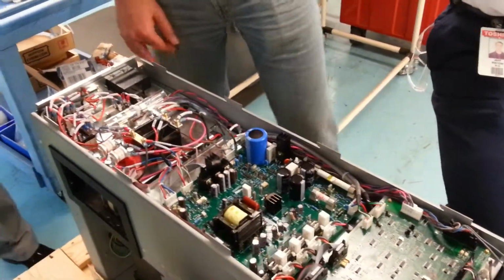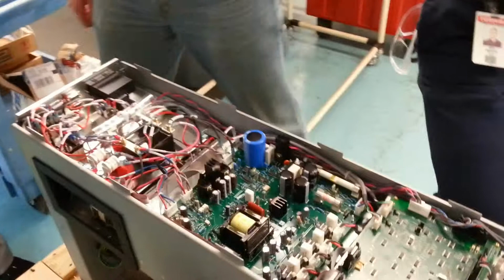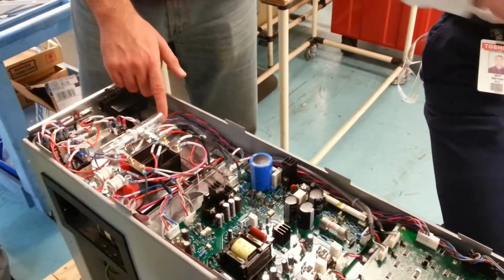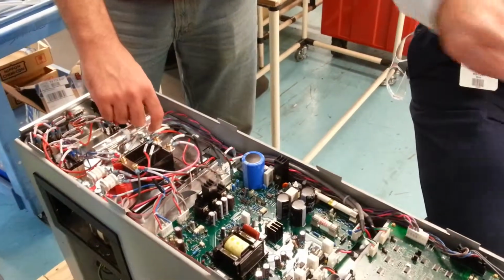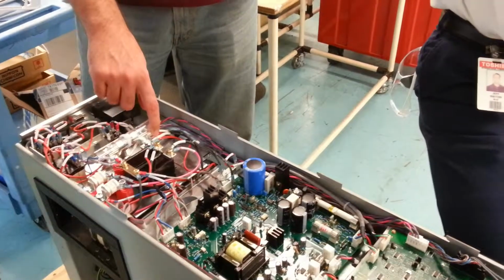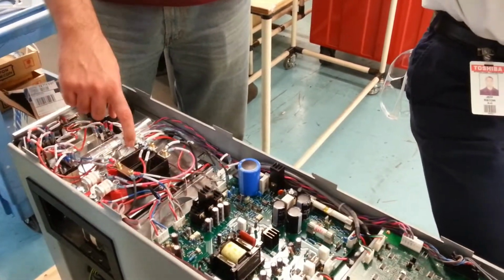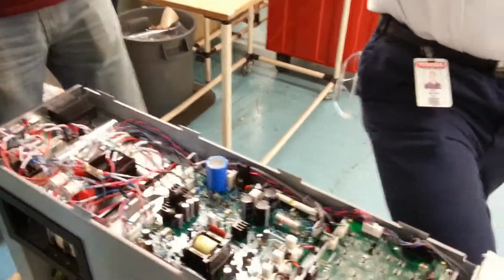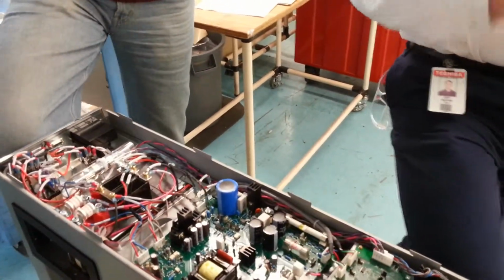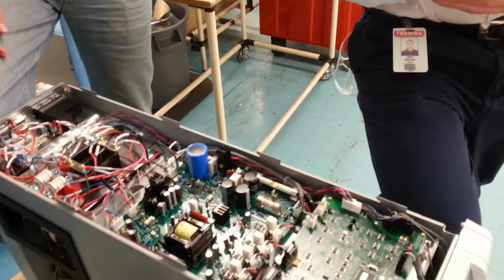With our G8000 line, some units run in the low 300s, and I've got one larger 500 kVA unit that runs at 480. Same chopper, same scenario, same frequency. It all comes down to the switching frequency, the time base, and the boost you want to convert up to, which is all software controlled. You tell it to chop to 500 volts, it'll chop to 500 volts.